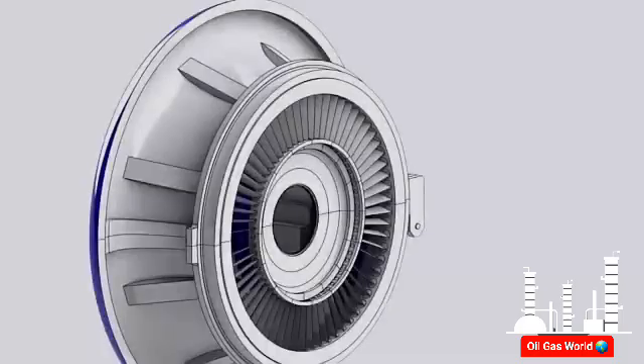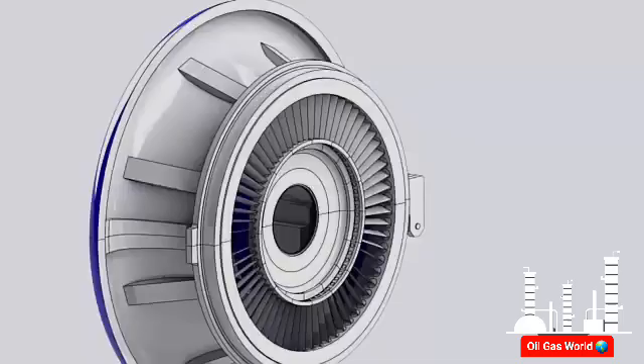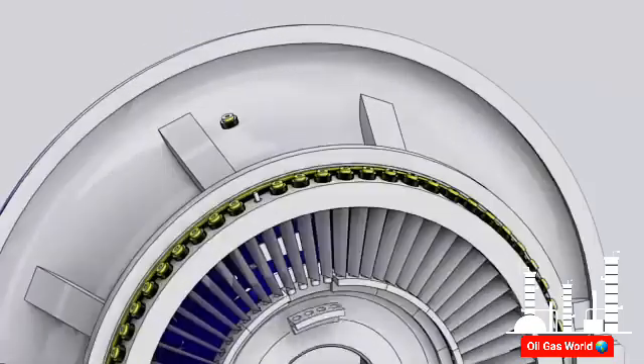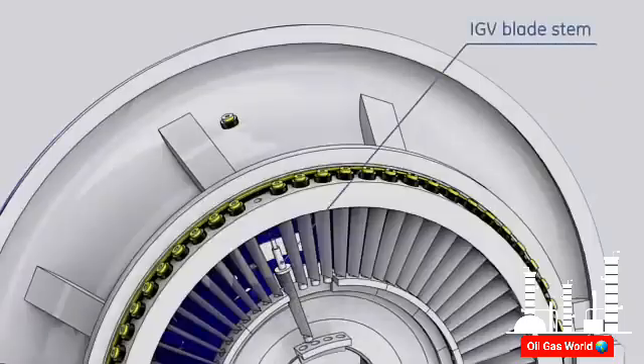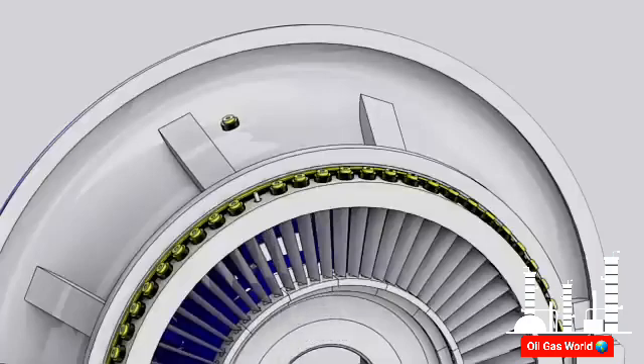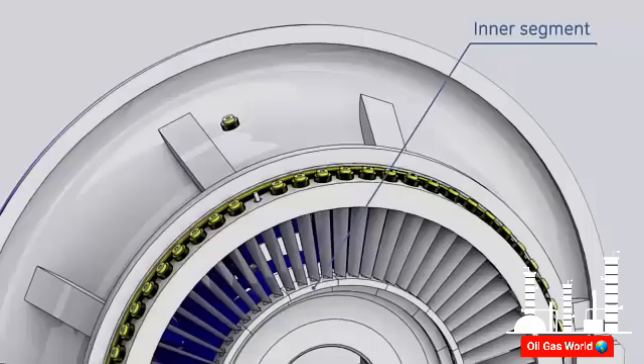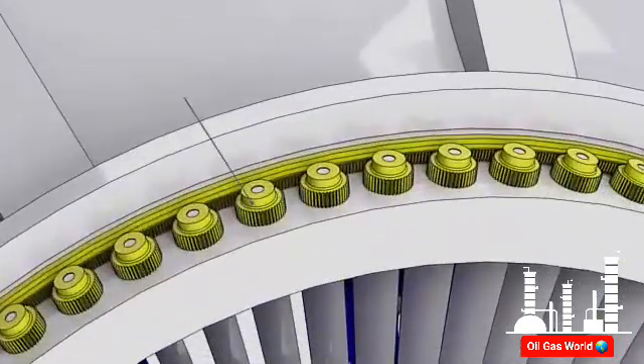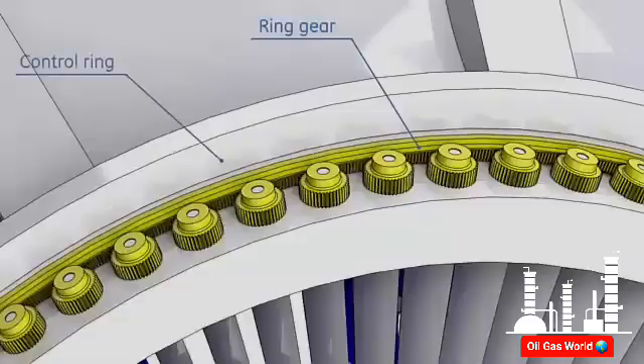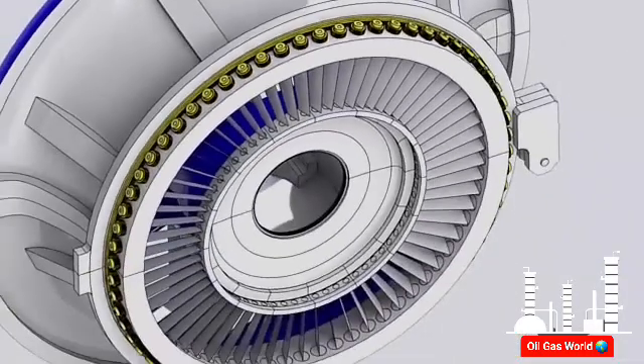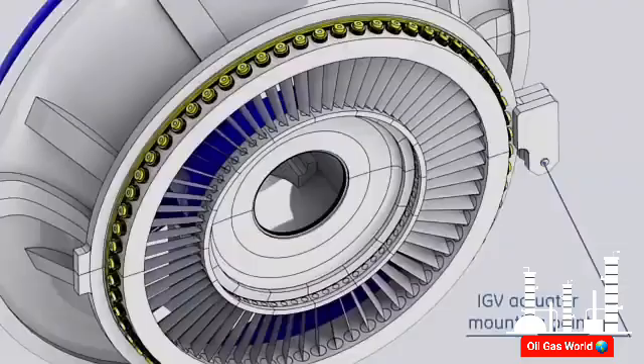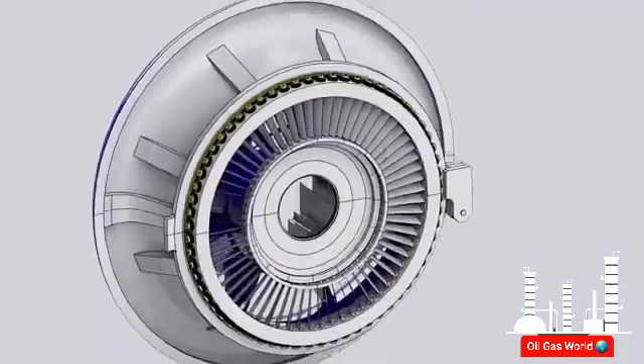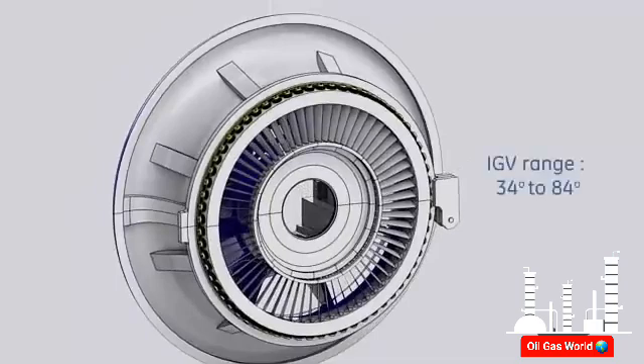Variable inlet guide vanes are located at the aft end of the inlet casing. Their function is to control the amount of airflow across the compressor. The total number of inlet guide vanes is 64 blades. Each blade stem is inserted into a hole machined on the inlet casing, with each four of them supported from below by one inner segment. A pinion gear is installed to each blade stem and keyed into position. These pinions are rotated by a ring gear assembled to the control ring. The control ring is positioned by a hydraulic actuator to obtain the desired inlet guide vane opening angle, which ranges from 34 to 84 degrees.